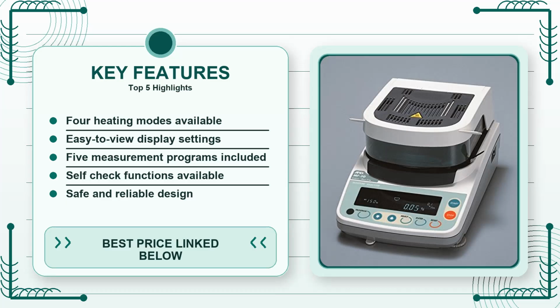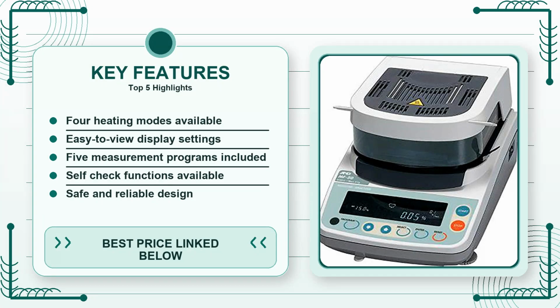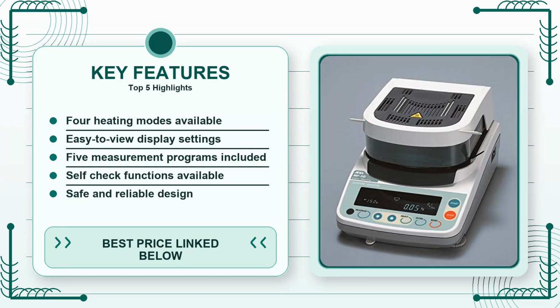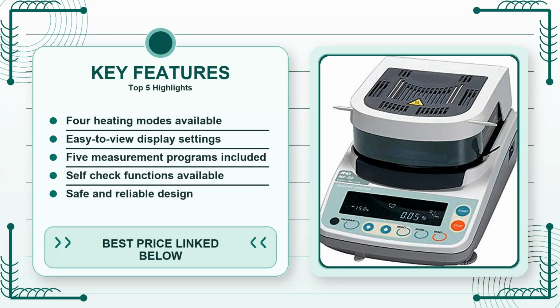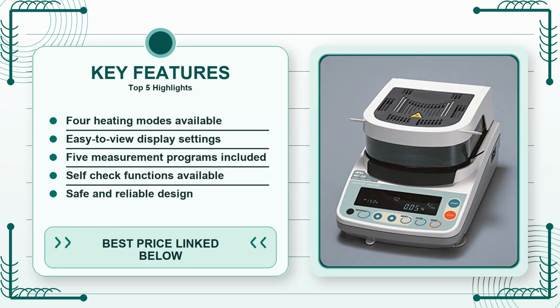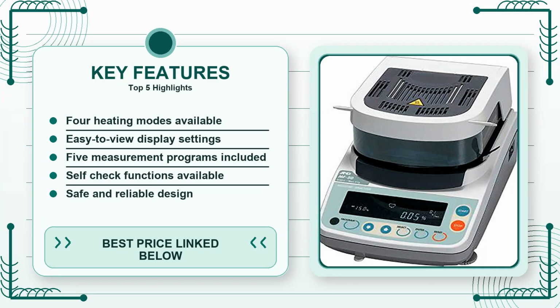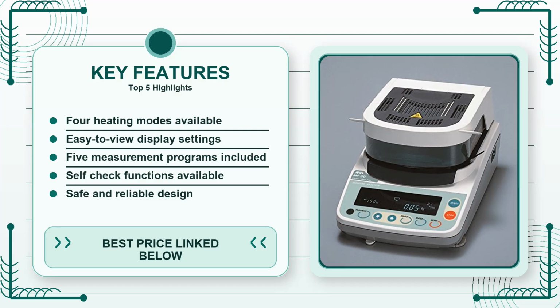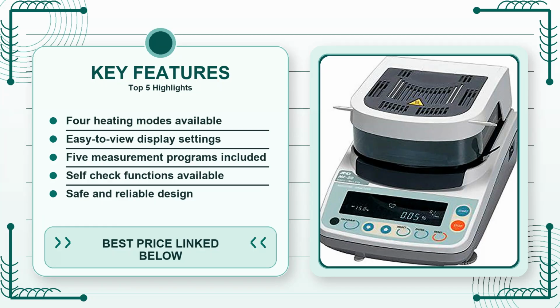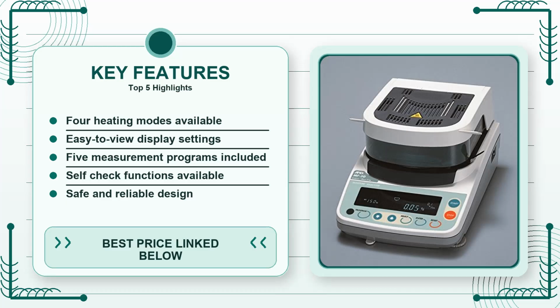Let's get into the practical strengths that actually show up when you're using the MX50 day after day. The first thing I noticed during my trial run was the heating uniformity. The 4 heating modes let you choose between a gentle ramp that avoids sample scorching and a rapid ramp that gets you to target temperature in under 2 minutes. In a food lab scenario, that meant I could dry a high-moisture fruit puree without creating a crust that would trap water inside, something that cheaper balances with a single heating setting often struggle with. The second strength is the clarity of the VFD paired with the progress window. When the weight curve flattens, the display flashes stable, removing any guesswork about when to stop the run. That visual cue is a small feature, but it cuts down on operator error, especially when multiple technicians are sharing the same bench. Now for the practical weaknesses that matter.